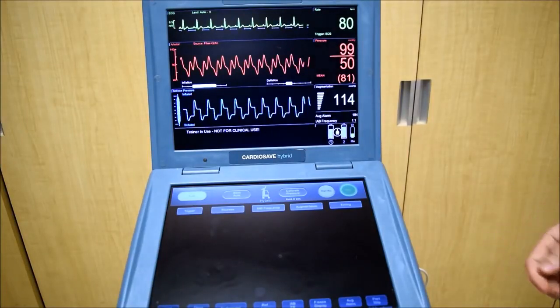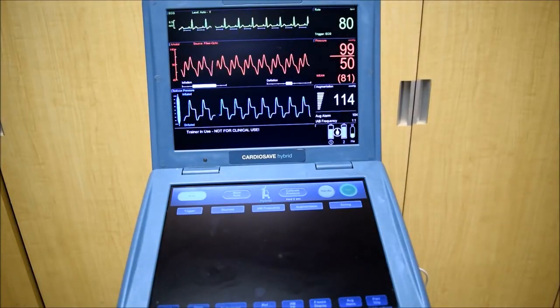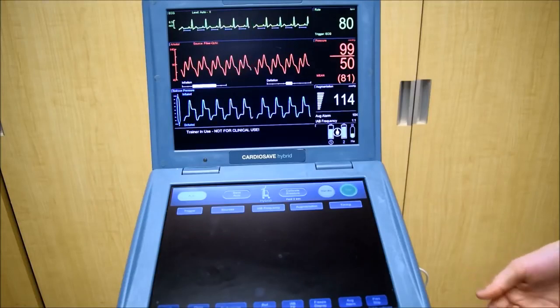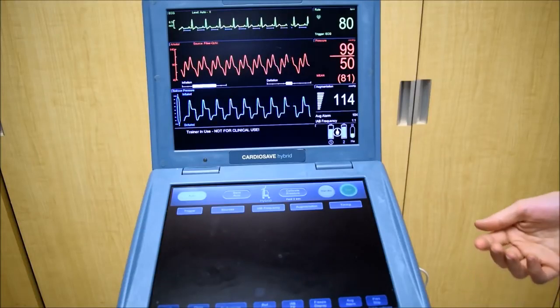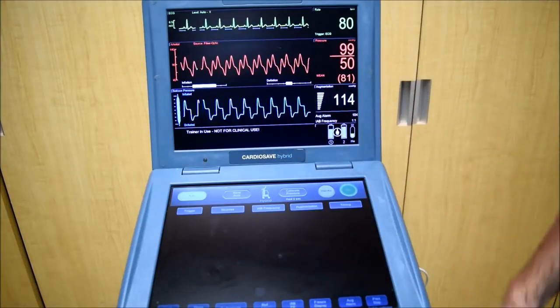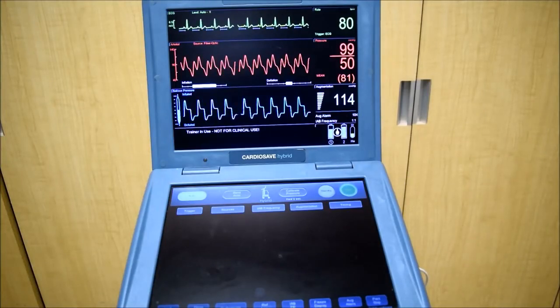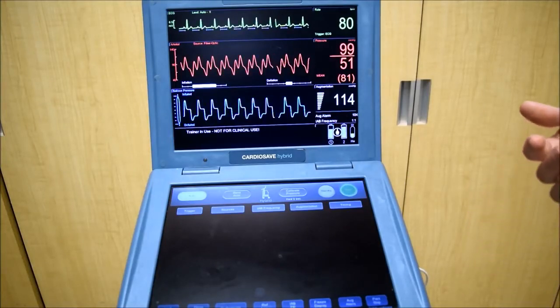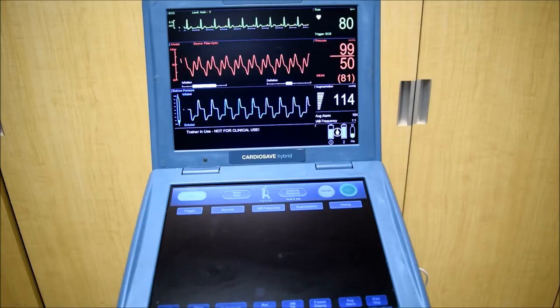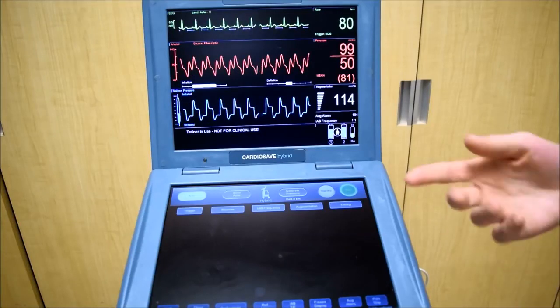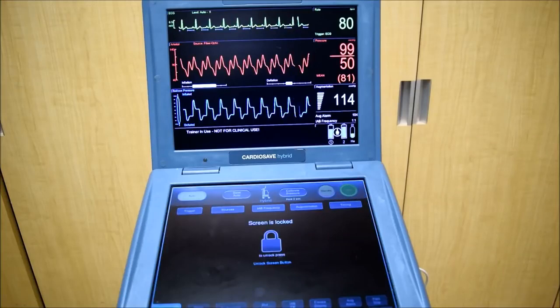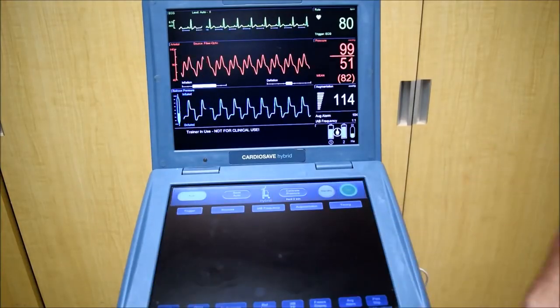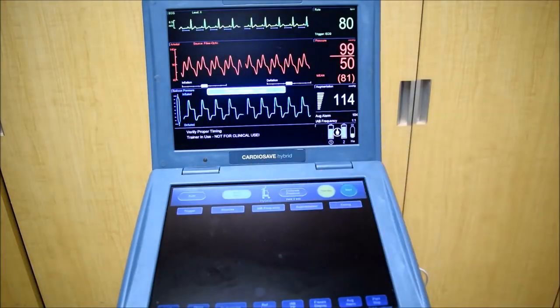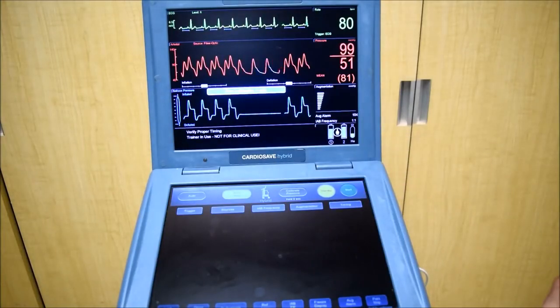Now that the balloon's on and our pressure transducer is zeroed, I'd like to time the balloon. You can do this one of two ways. You can do it in auto mode, which it's currently in, and this is really nice for time-sensitive situations. If you need the balloon to get going quickly, this is the setting to use. However, if you want something more accurate, we can time it ourselves in semi-auto.